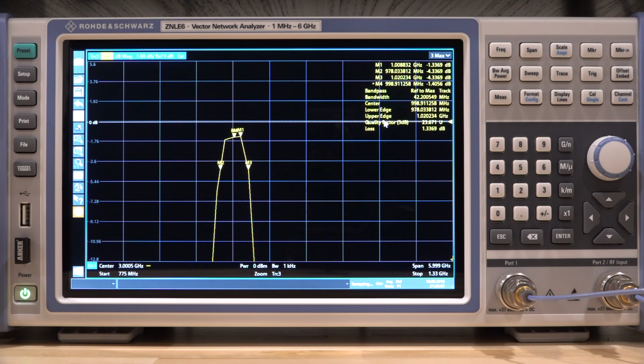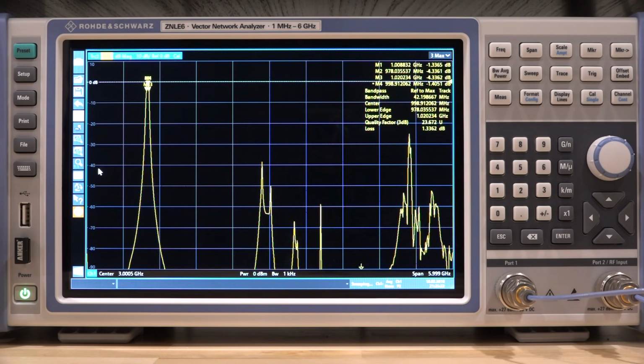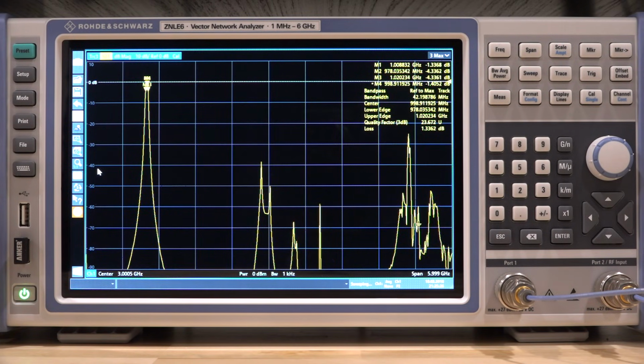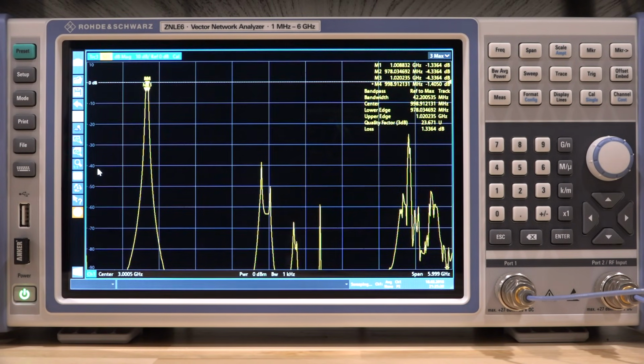And the lower and upper edges are also labeled. So the quality factor of the filter, given its center frequency and bandwidth and the drop-off ratio and all that, is a factor of 23.6 and a loss of 1.3 dB. So we have essentially all the important characteristics of this filter being done automatically by the instrument. So let's zoom back out and let's go ahead and change the frequency response by changing the filter center frequency. So right now we're at 1 gigahertz. Let's go ahead and move it to 1.5 gigahertz and see what happens.